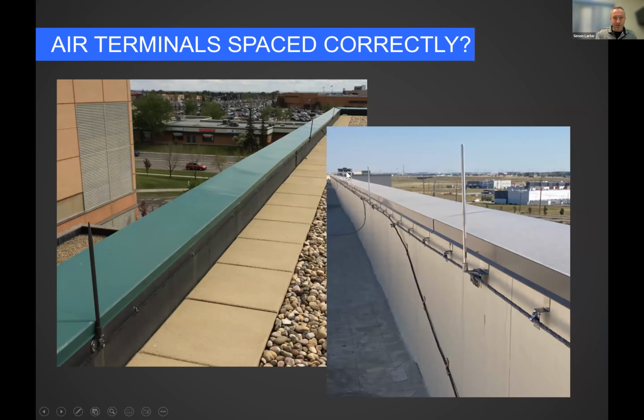Let's move on—are the rods spaced correctly? On the right, that's another warehouse job, and yes, every 6 meters there's a lightning rod sticking up. On the left, though, those rods aren't 600 millimeter rods, which would allow for 7.6 meter spacing—they're shorter than that, so they'd need to be spaced every 6 meters. They're definitely not; they're probably closer to 8, 9, or 10 meters apart.